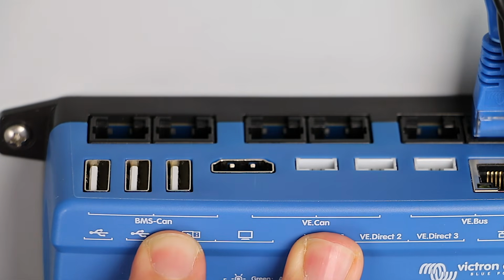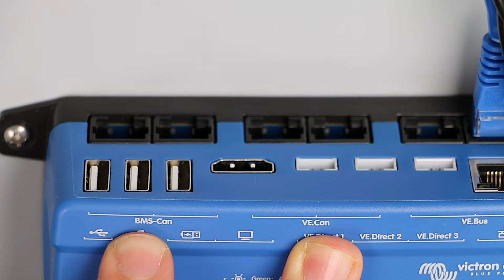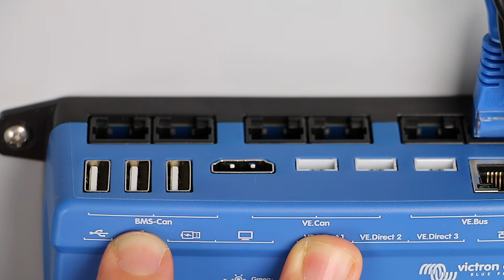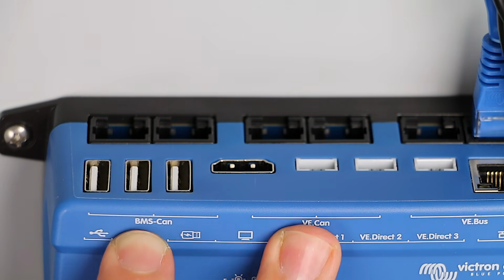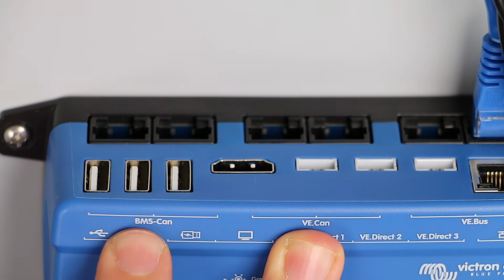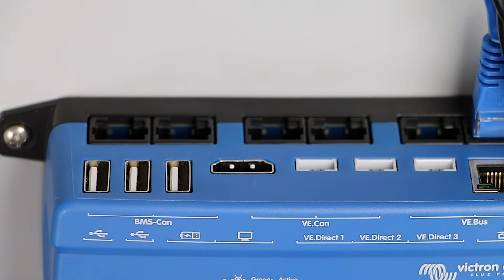These are CAN buses. The BMS CAN is something from the older Cerbos where it's automatically set up for the BMS protocol, which is 500 kilobits per second. But in the newer Cerbos and the Ekrano, you'll see VE CAN 1 and VE CAN 2, and basically we need to plug into either one. The main thing is we're going to program it in the Cerbo, so it doesn't matter where we plug in.